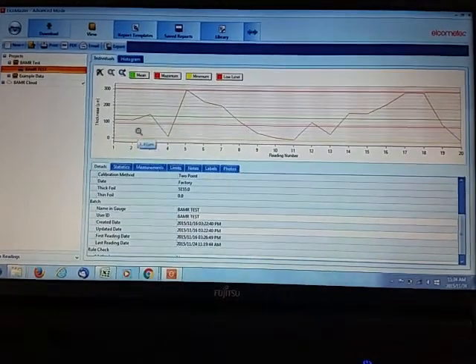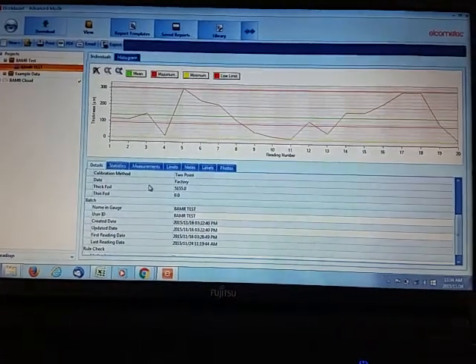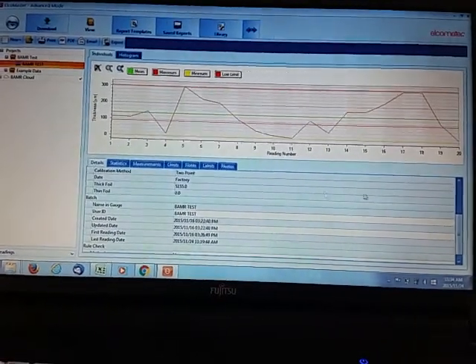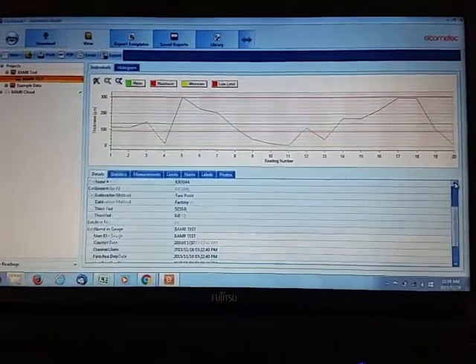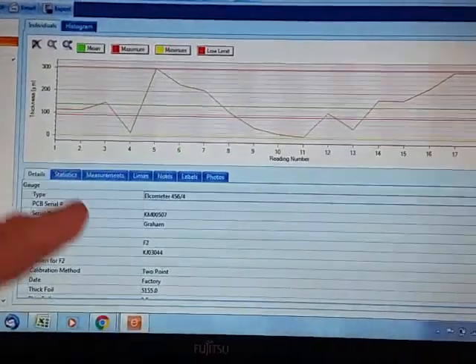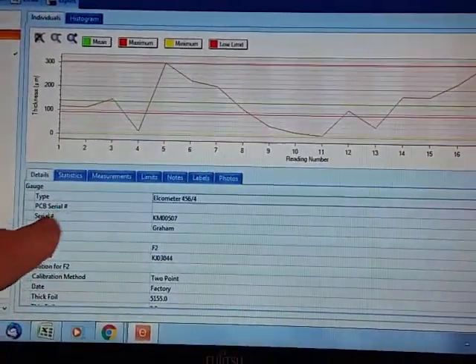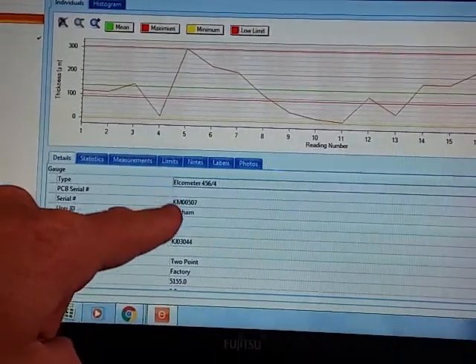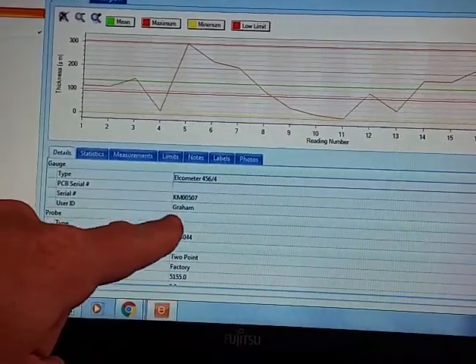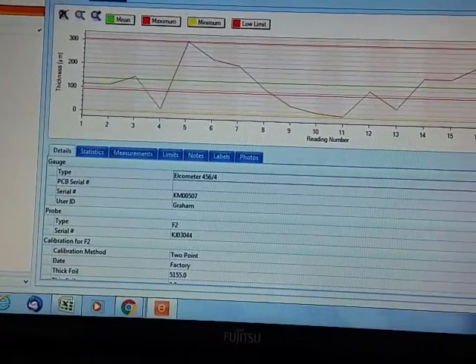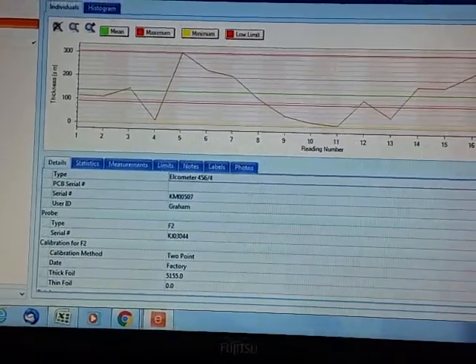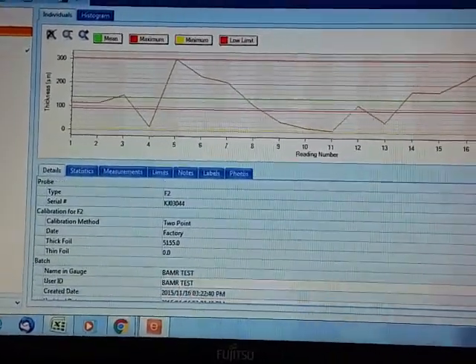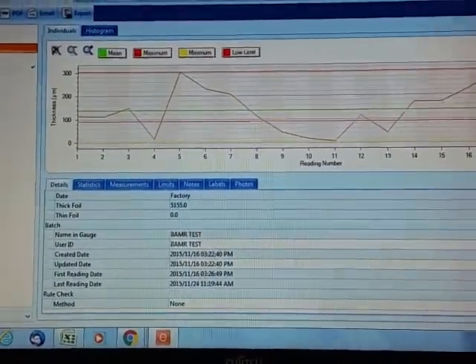Okay, so we have our 20 readings that have been downloaded. Here are some details of the readings: the instrument type, the serial number, the user ID which we entered earlier, the probe type, the probe serial number, and a couple of calibration details.